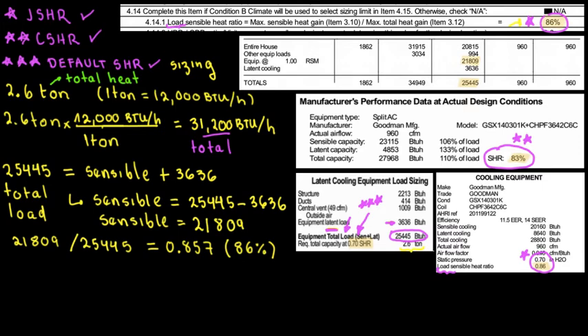In other words, the 0.86 is what we already know: the J sensible heat ratio, the load. The 0.70 is not the J or load SHR — it's how we size the equipment, our recommendation for sizing. Now let's talk about the 2.6 ton and 31,200 BTU per hour, and how we use the default sensible heat ratio.